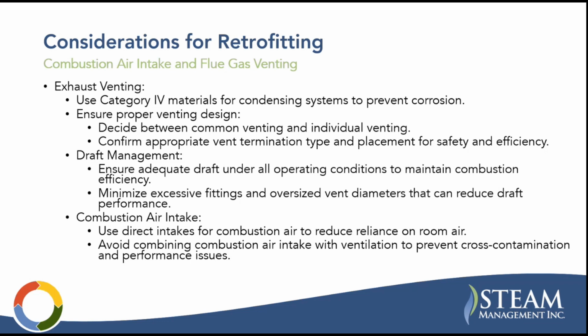As far as your combustion air intake, well, there's two options. You can either use direct intake, which is where you're piping your combustion air in from the outside, or you can use room air. But what you don't want to do is combine combustion air intakes, as the boilers can kind of pull on each other and cause cross-contamination and performance issues on the air supply. So you can use a common vent for the exhaust, but you do not want to use it for the combustion air.